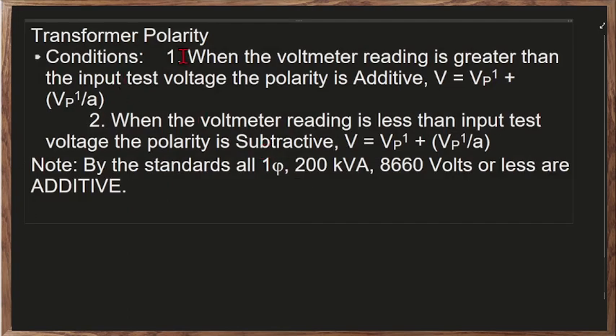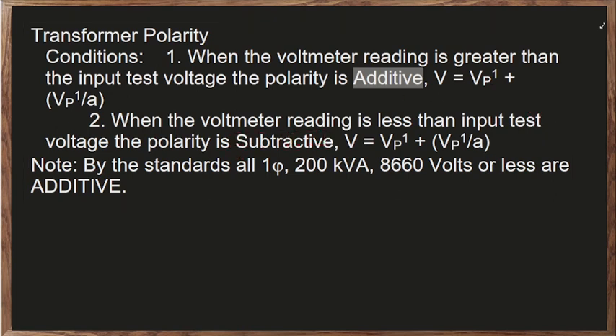Okay, so transformer polarity. When the voltmeter reading is greater than the input test voltage, the polarity is additive. So when the voltmeter reading is larger compared to the input test voltage, the polarity of our transformer is additive. If the voltmeter reading is less than the input test voltage, the polarity is subtractive, no?